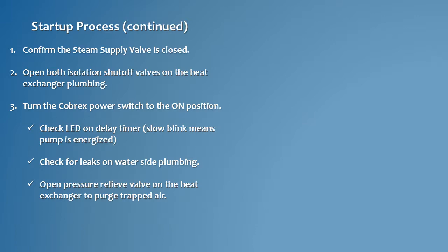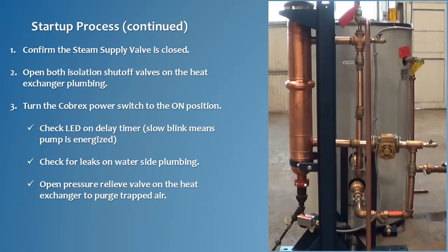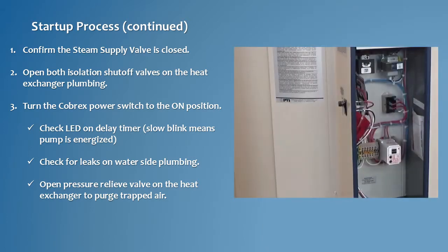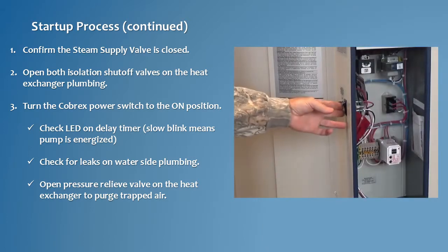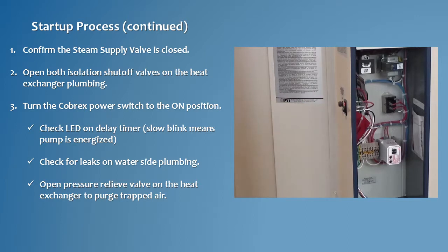Begin by confirming the main steam supply valve to the water heater is closed and that there is no demand on the system. Open both isolation shutoff valves on the heat exchanger plumbing. Turn the power switch to the on position to energize the circulating pump and condensate control valve. Check both for proper operation.